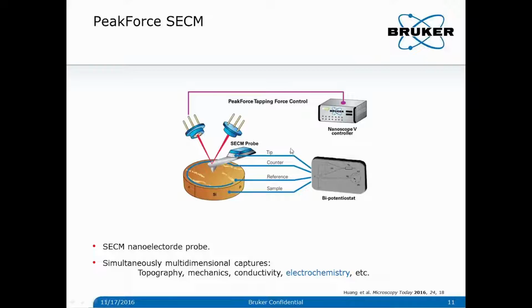So you can see that in this bipotentiostat configuration, we have 4 electrodes, and the tip and the sample are both working electrodes sharing the same counter and reference electrodes. Combining with AFM, especially with peak force tapping technology, peak force SECM is capable of capturing simultaneously multimodal information such as topography, mechanics, conductivity, and electrochemistry. And because it is using a nanoelectrode, it allows an electrochemical resolution below 100 nanometers, which is an order of magnitude higher than conventional SECM using a micro tip.